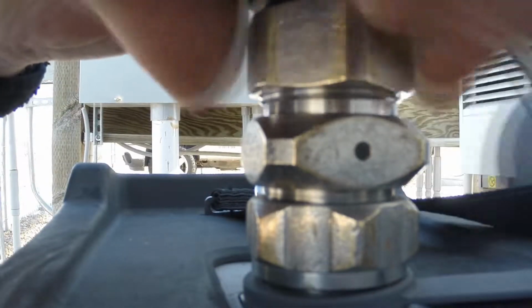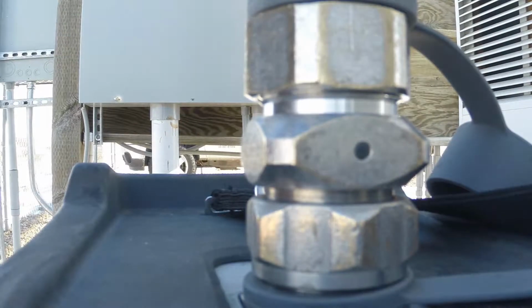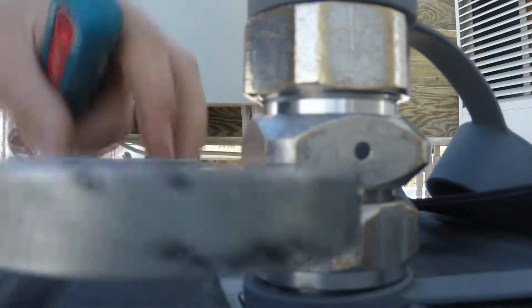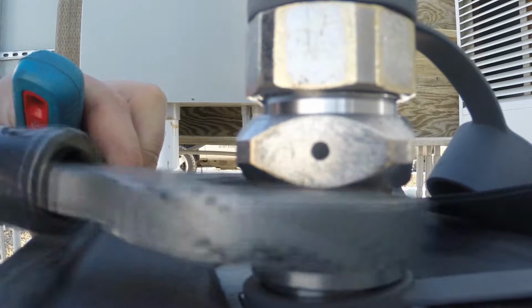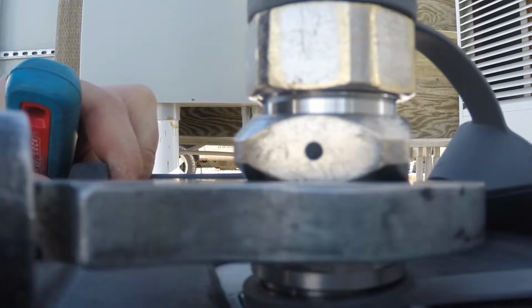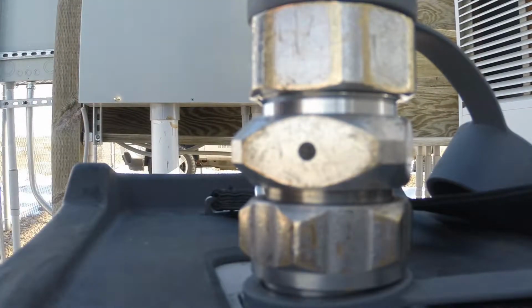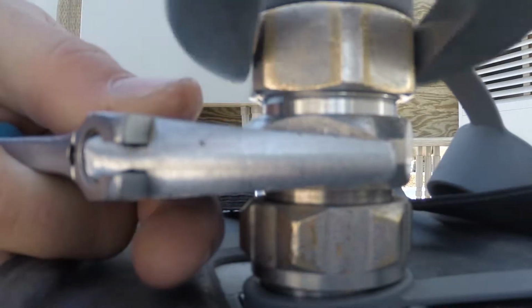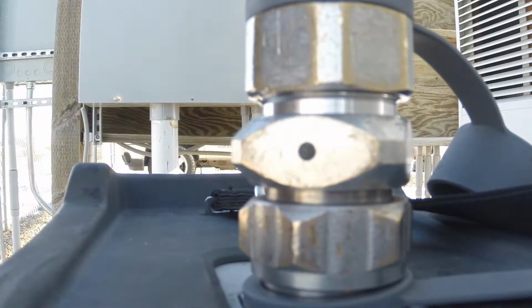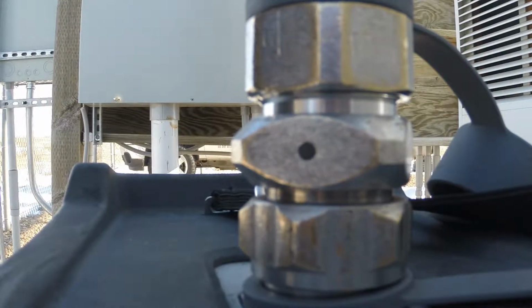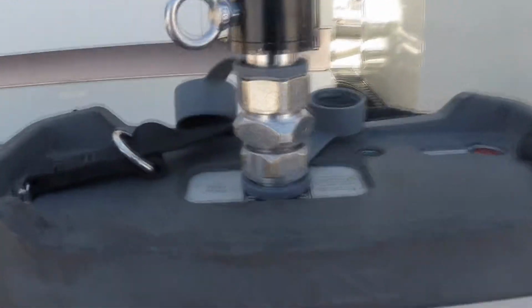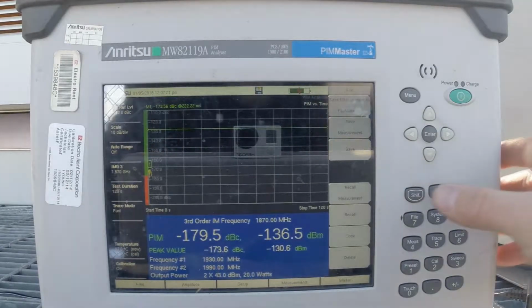We'll put our PIM load on top, and I'm actually getting a little ahead of myself. But we'll torque down our PIM standard, and to torque the PIM load onto the standard, we hold the square portion here and torque down that. If you don't hold that square portion, usually you'll end up over torquing it, which will give us issues also in the long run. So we have our PIM standard in line with our PIM load, and it'll actually tell us all this.